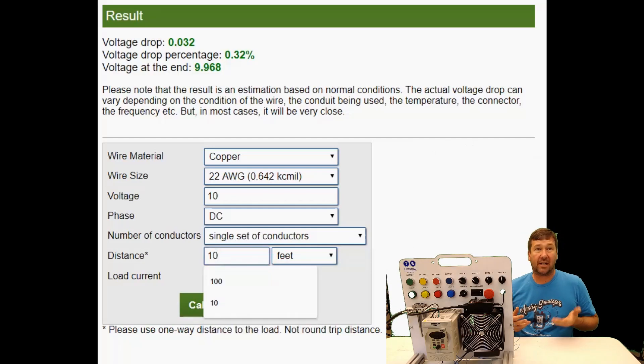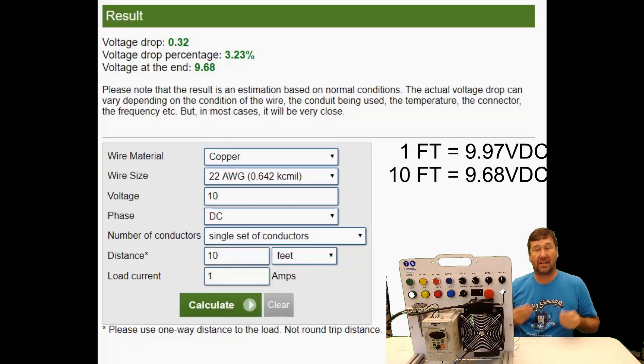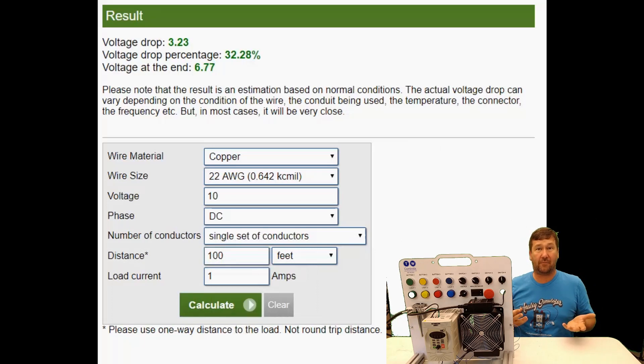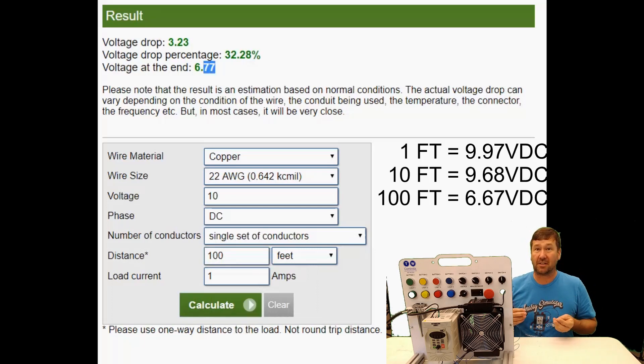If it's 10 feet long, it's going to be 9.68 volts or 0.3 volts less than before. Now let's make it 100 foot long, which isn't that unusual for a field instrument. The voltage on the other end is going to be 6.77 volts.